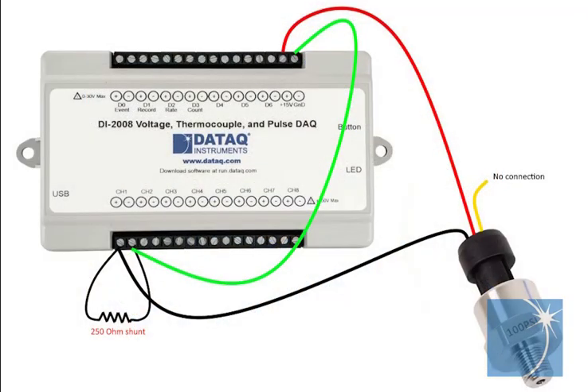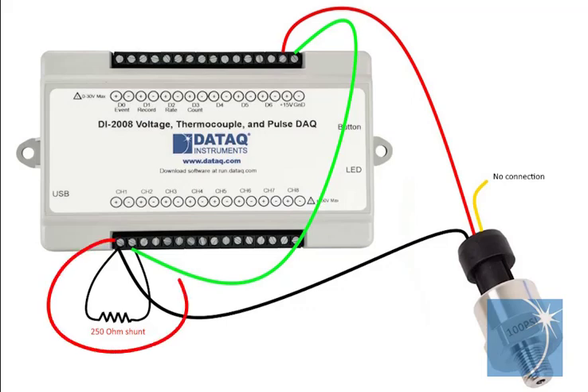We'll begin by connecting the pressure transmitter to the DI-2008. Note that we've connected a 250 ohm shunt resistor across the analog input, in this case channel 1.